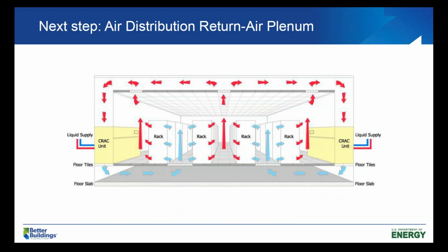Okay, so here's a better approach to help improve air management, and that is you've got the underfloor, the typical underfloor plenum where the cool air is supplied. It comes up into the cold aisles, it passes through the IT equipment, and then rather than returning just through open space, we use the above ceiling space as a return air plenum. We put perforated grills above the hot aisles to facilitate that airflow, and then the CRAC or CRAH units, that's computer room air conditioner or computer room air handling units, pull that air out of that plenum and cool it for return to the underfloor space. Next slide.